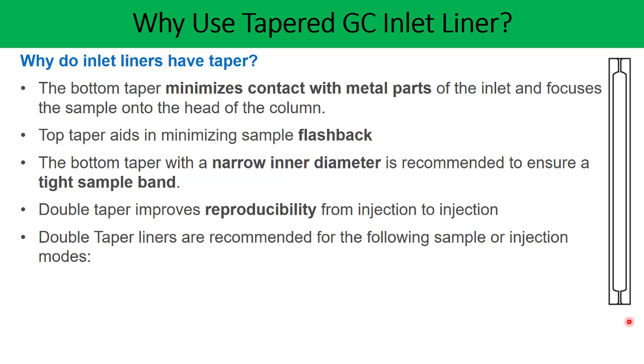Double taper liners are recommended for the following sample types or injection modes. First, in the case of trace level analysis where the concentration of the analyte is very low, this taper design helps to achieve more recovery and transfer of the sample onto the column, so it is always preferred for trace level analysis. Second, the splitless mode — because of its design, it has very low sample transfer from the injector port onto the column.